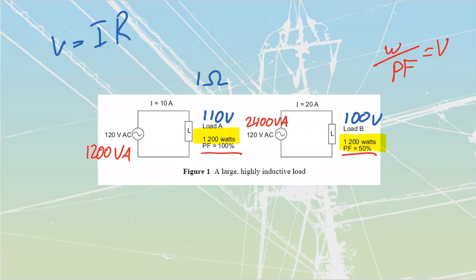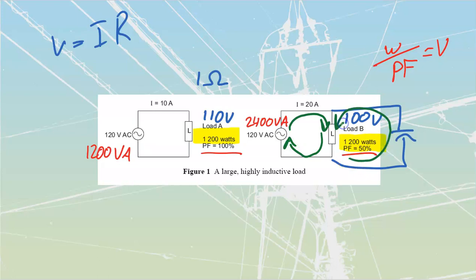If we fix this one over here, if I can take what I've got happening inside of here and make it like that, then I'll have done what's called power factor improving. Really what I would be doing, if I've got an inductive load, is adding another capacitor onto the system. That capacitor is still going to carry current, but now this current up here is going to drop. If I can improve to 100% power factor, what I'll see is that I'm sending 10 amps through this loop over here, and the other 10 amps is coming through here.